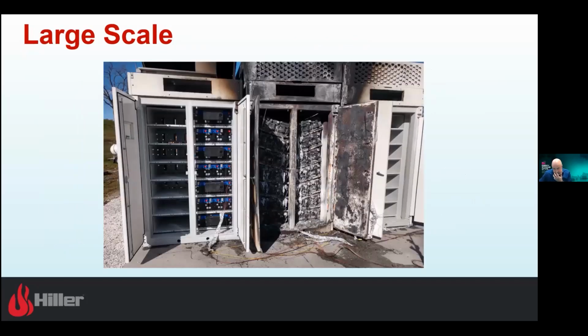This is a good example of a large scale fire test. What I consider very positive on this is they lit the whole unit up and the whole unit burned, but if you look, what's right next to the batteries, they're in good shape. We got up to 2000 degrees C in this container, but the batteries next to it didn't get above 50 degrees C. That means they may not be viable coming out, but they certainly didn't propagate and didn't catch fire. And if you look at the spacing on this thing, there's only about 6 inches between containers.